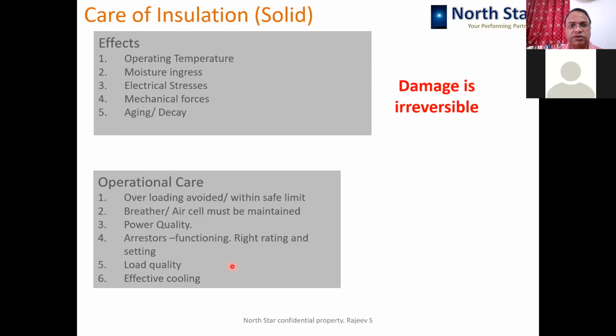So basically, more or less, the solid insulation gets affected by three or four factors: the operating temperature, meaning the load on the transformer and ambient temperature, moisture ingress, and electrical stress. If we can control these reasonably, then we can avoid permanent damage to the solid insulation.